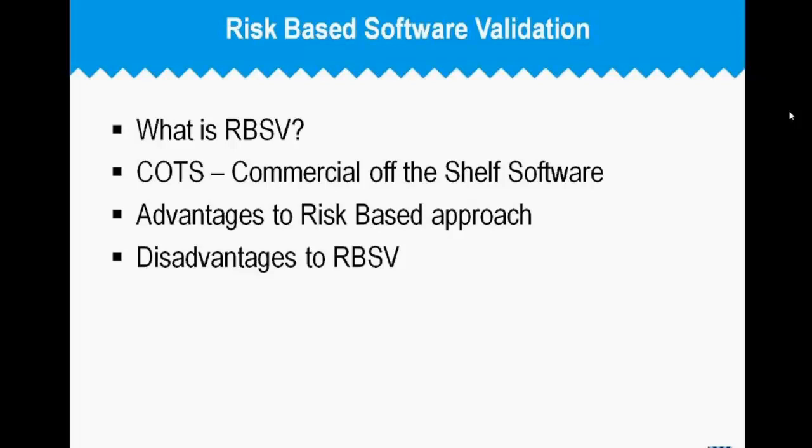In my experiences with different companies around medical devices, this is usually a blind or a concern spot. There's lots of things that are incorporated inside the software stack, the application stack, that are commercial software where we have no idea what the content is. And frankly, the agency wants some demonstration that you understand what you're doing, that you've made some assessment and confirmed that it's appropriate to use that particular product with all its flaws inside your particular software device, medical device. And they're looking for evidence that you've applied some type of engineering assessment and you have evidence that it's appropriate.